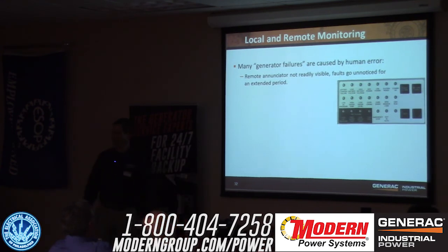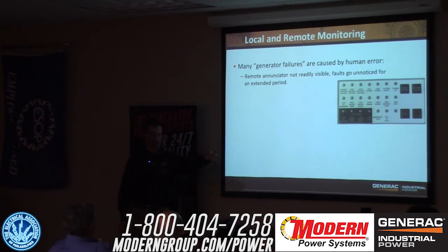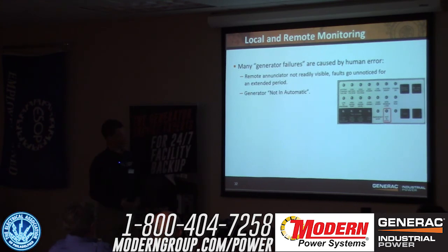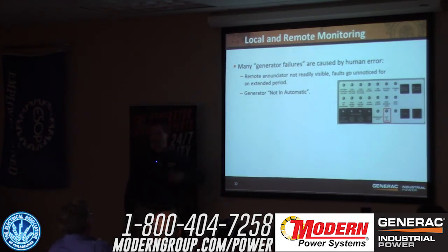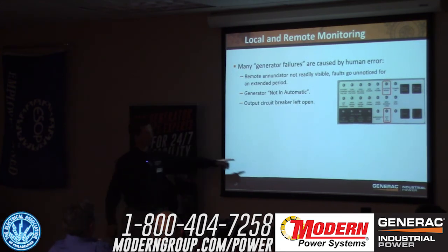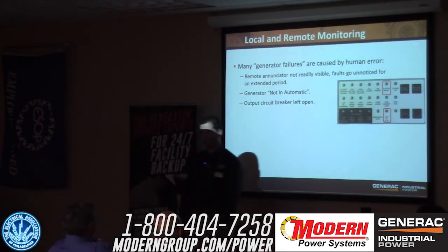Put the remote annunciator where somebody can see it. A lot of times we'll see them mounted near the fire panels—that's a good spot because it tends to get traffic. Put it in the maintenance manager's office if there's somebody there. The point is, put it somewhere somebody's going to see and look at it regularly, because a generator not on auto—that's an easy one to fix. Output circuit breaker open—it happens.